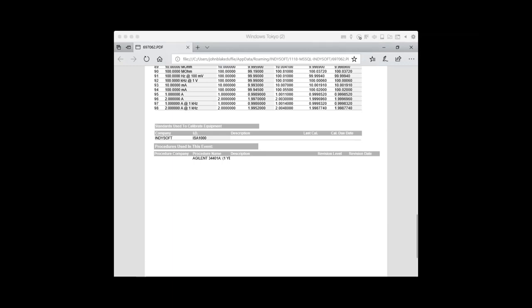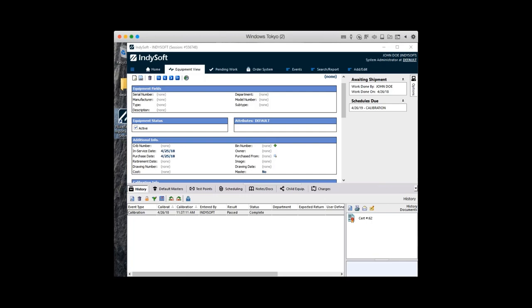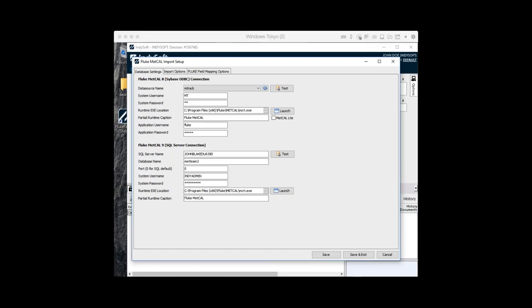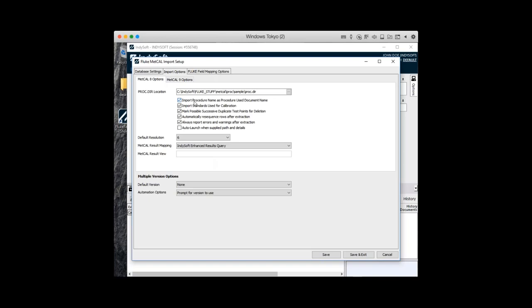That entire process is exactly the same for MetCal 8 or MetCal 9. So again, if you're on one version or the other or in transition, there's nothing else to relearn — the functionality works the same either way. Now we've gone through basic daily use; we're going to go through some setup options. The database setup screen is basically where you will point to your MetCal 8 or MetCal 9 database. We have the capability to refresh your ODBC data sources, test the data connection, and even test to make sure you're pointed to the runtime. The second option gives you the ability to import procedures and standards, automatically resequence — taking out all those gaps in the import process — and set default resolutions.